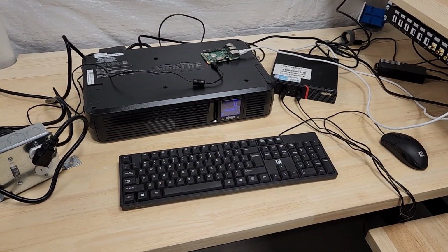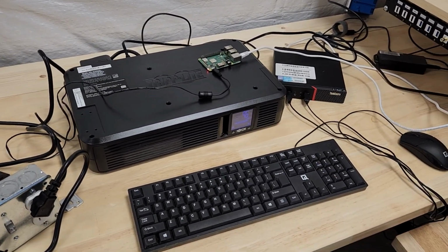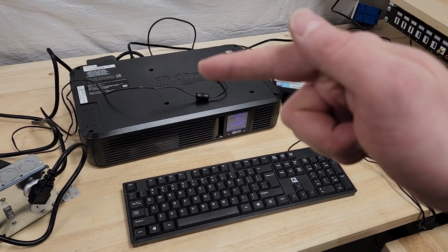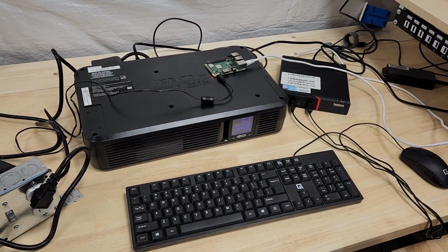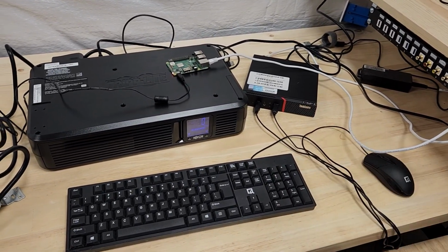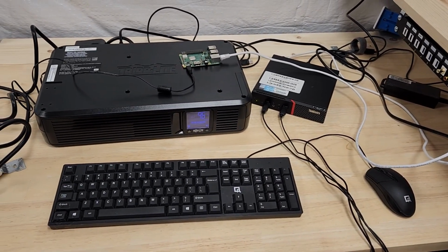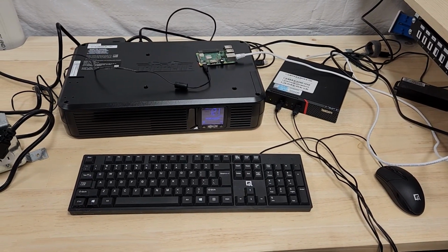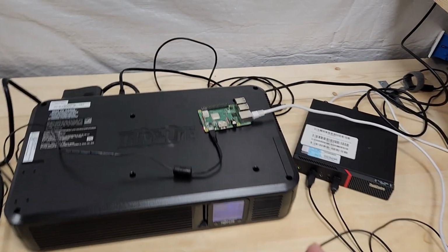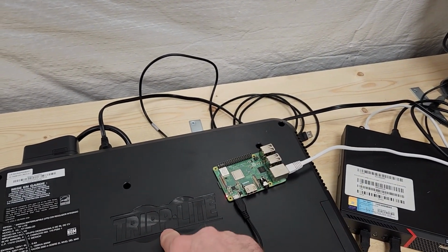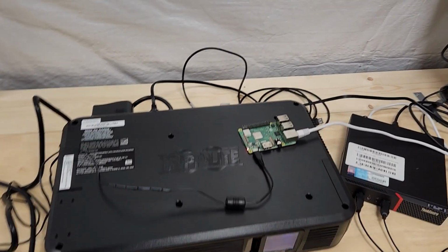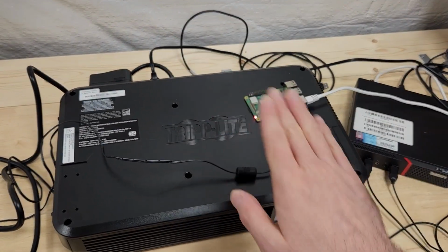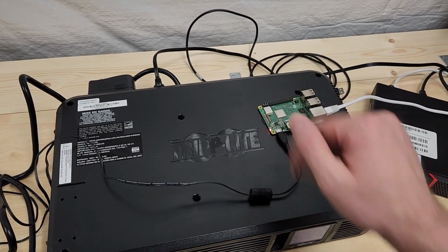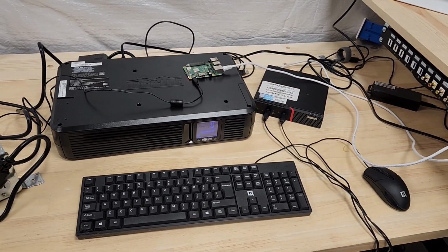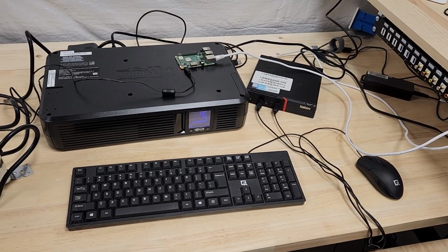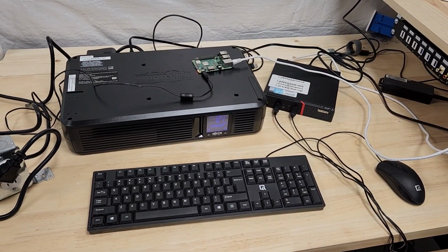Basically, you can install some software on a machine that acts as the server or host, and you plug that in to the UPS with a USB, and other machines can actually listen to the server with a client version of the software and know if they should power themselves down. So basically what happens is you have one machine plugged in via USB to the UPS, and you can have as many others as you want listening to determine the state of things. And when this thing goes into battery mode, the server can tell all the clients, hey, you guys need to shut yourselves down because we're on battery mode. And that's how I'm going to have my servers behave in the rack. So let's get that set up and I'll walk you through it.